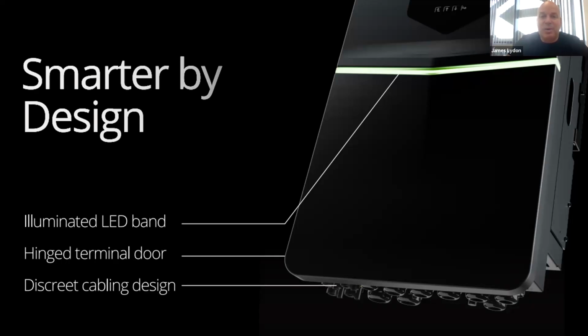You can probably see on the image there, we've got the illuminated LED on the front of the unit. That can be set to different things, so it can show the battery SOC, what the maximum load is, if there's any faults, or it can simply be turned off. So it is quite customizable. There's a hinged terminal door on it. So with the current inverters, the Ecos and the Classics, the installer has to remove the panel, whereas with this, it's a hinged door, so it is easier to access. And with the lip at the bottom of the inverter, you don't see the glands underneath it, so it does look a much sleeker install.